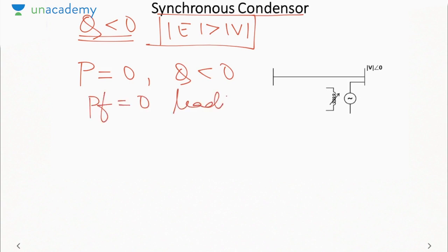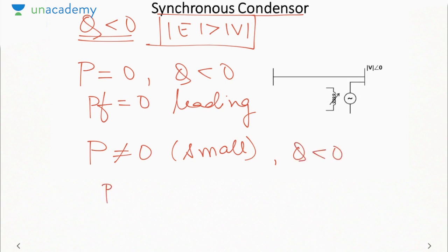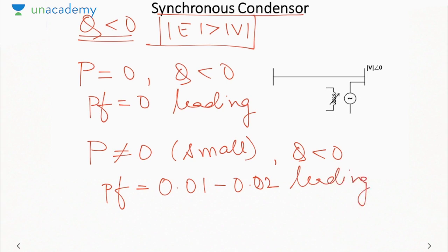leading. But if we talk about practically, P is not equal to 0, but it is small because real power will be consumed to supply the losses. So Q will be less than 0. So power factor practically is 0.01 to 0.02 leading. There will be small real power which will be supplying the losses in the synchronous machine. Since it is working as a capacitor, it is acting as a shunt capacitor. So it can be used for power factor correction.